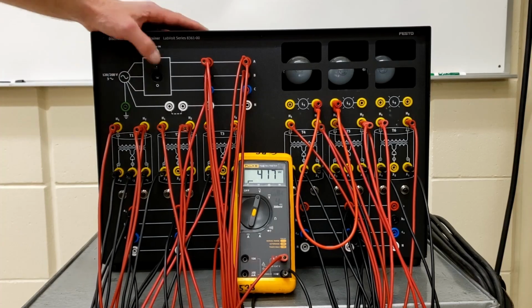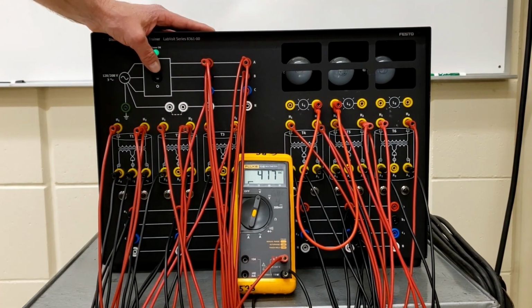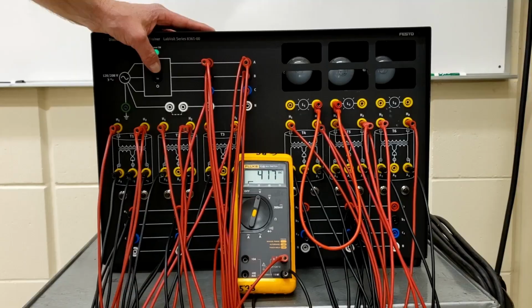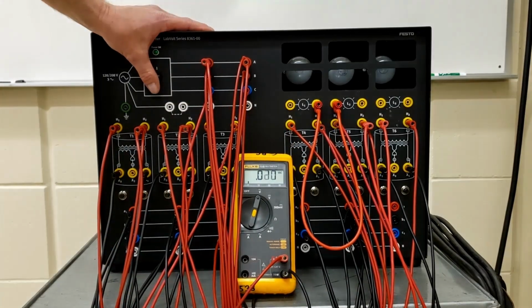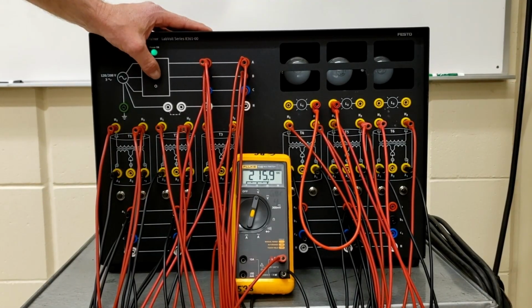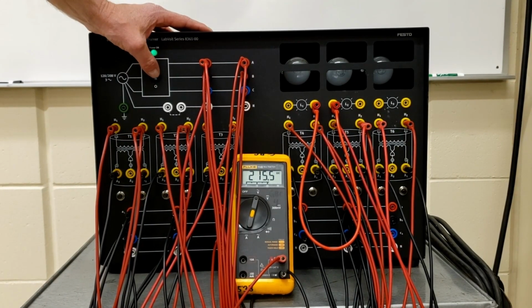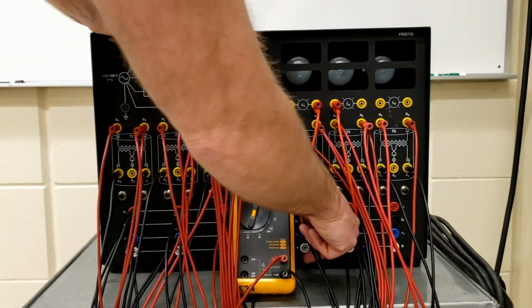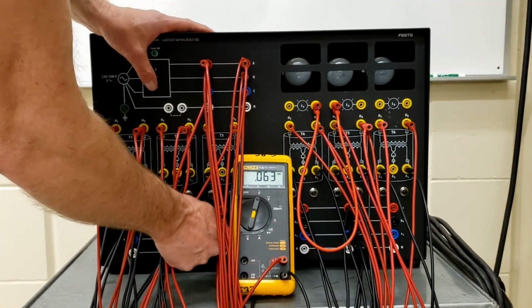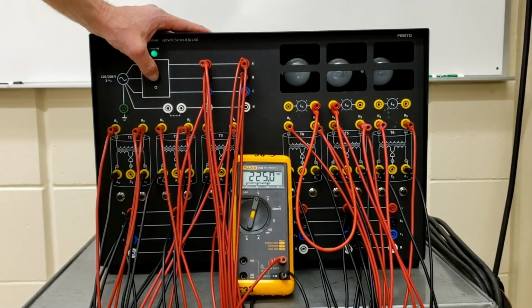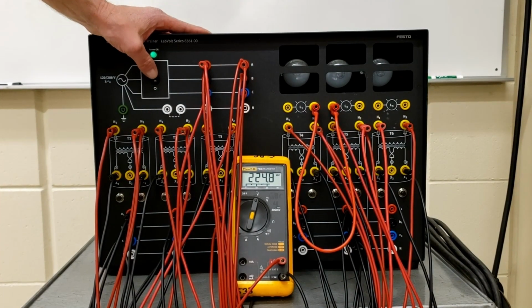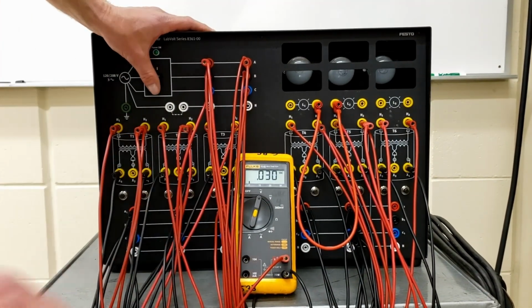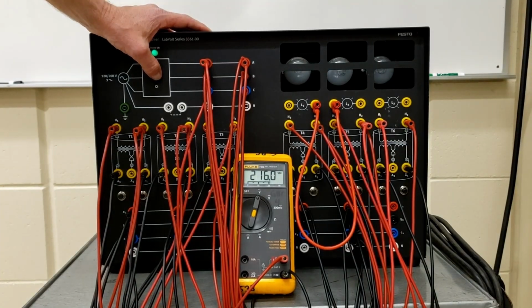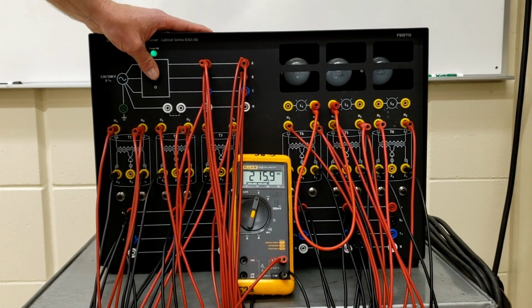What's interesting is that these voltages appear when X2 is grounded on either one of the transformers. If I remove that X2 connection, you'll see the voltage between each of the lines now looks like 215 between these two C phases. On the B, I got 224 - these are now floating voltages with no reference to each other, and they're fairly similar to each other. There's 216 on the A as well.